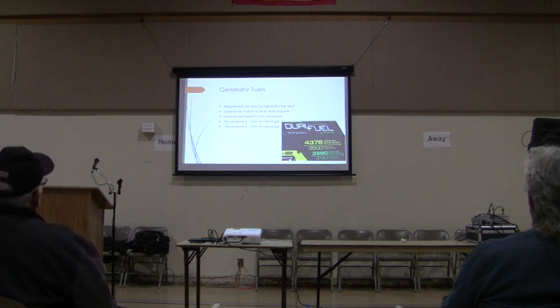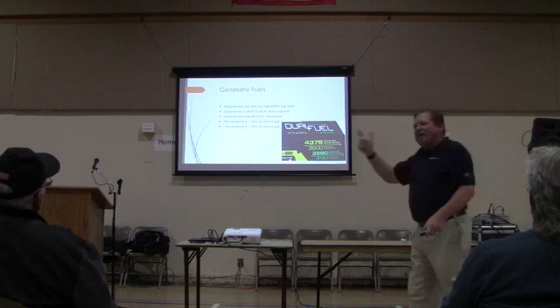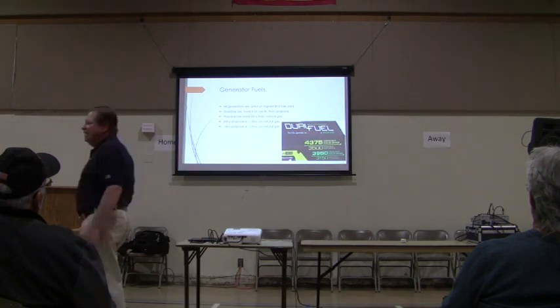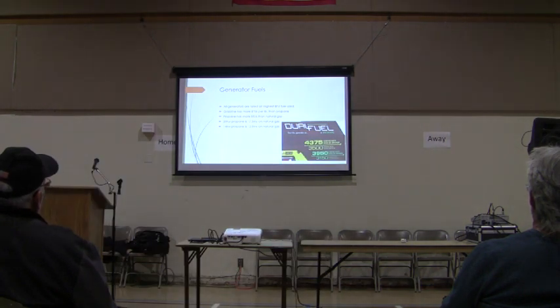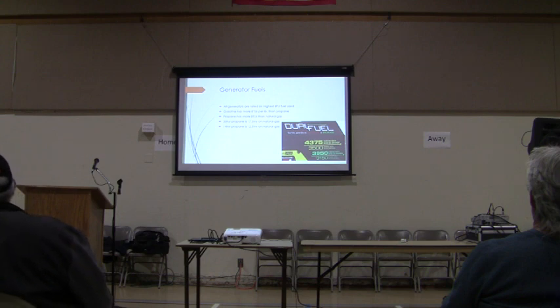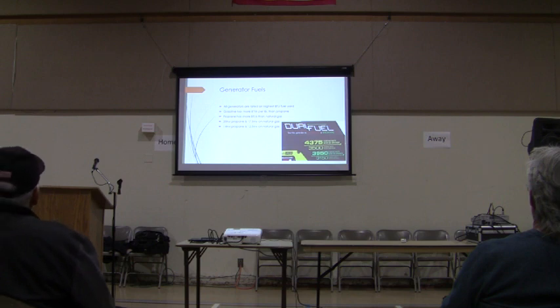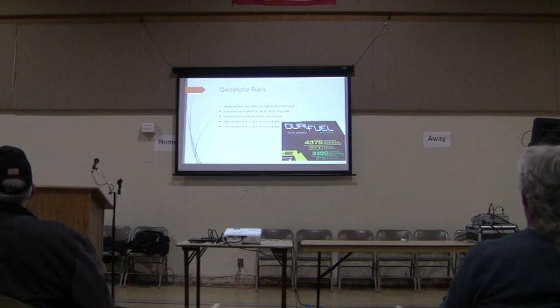The same thing happens with propane and natural gas for standby generators. A 20 kW natural gas generator is only going to give you 17.5 kW on natural gas. It's rated for propane. A 14 kW generator will give you 12.5, because propane has more BTUs per gallon, or per cubic foot, as they rate with appliances.